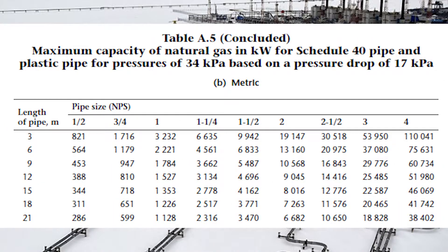Much like the low pressure gas line sizing tables, there is a metric equivalent, and that will be the table called concluded — in this case, Table A5 concluded. It covers maximum capacity of natural gas in kilowatts for SCH 40 pipe and plastic pipe for pressures of 34 kPa based on a pressure drop of 17 kPa. Note that the length of pipe is in meters, the nominal pipe size is still in inches, and all the values in the table are in kilowatts.